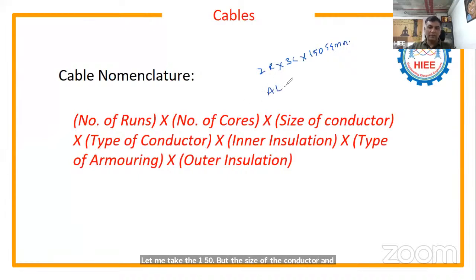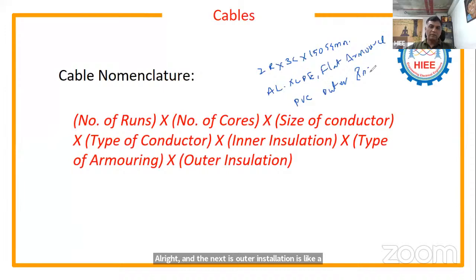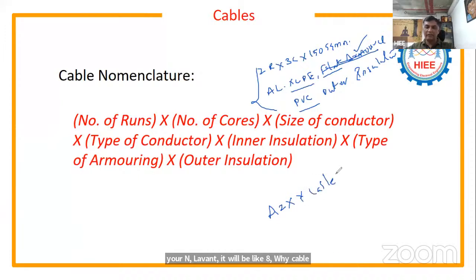And the type of conductor: let me take aluminum conductor with XLPE inner insulation, and the type of armoring is flat armored, and the outer insulation is PVC outer. It depends; every cable will not be the same. It depends upon the requirement, which should be the inner insulation, which should be the outer insulation, and whether it is flat armored or wire armored. Sometimes we go with cables without armoring, wherever there is no mechanical protection to the cable. If there is no flat armoring, then your nomenclature will be like A2XY cable. There is no F because we are not using any flat armoring.